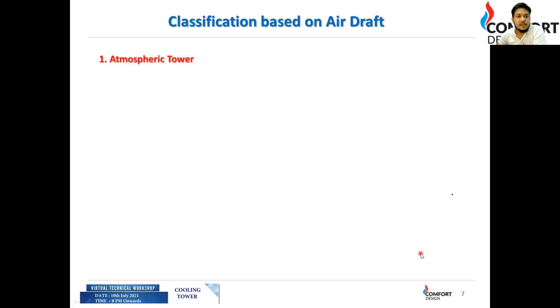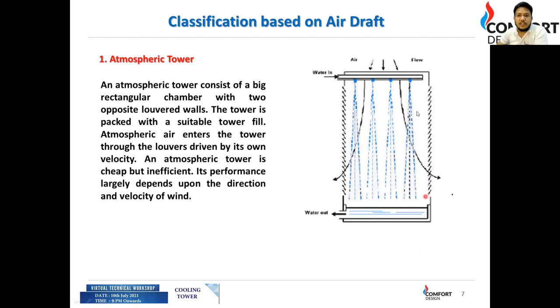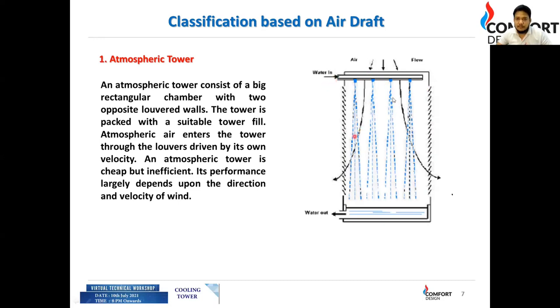Classification based on air draft: the first type is the atmospheric cooling tower. These are erected at the site and typically found in oil and gas industries, refineries, and manufacturing plants. An atmospheric tower consists of a large rectangular chamber with two opposite louvers. Atmospheric air enters through the louvers driven by its own velocity. It is cheap but inefficient, and its performance largely depends on wind direction.